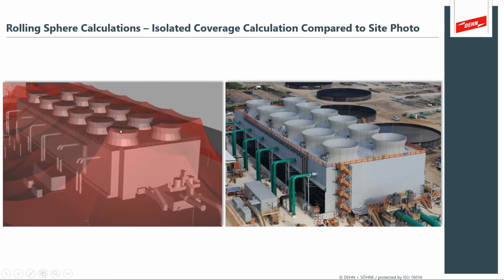So here's a nice illustration of the calculated coverage. This is what the theoretical coverage of that lightning protection system will provide, and then an actual photograph of the finished system. It's a little hard to see in this photograph, but you can see the air terminals are actually mounted on the light poles because the customer doesn't want us to apply a lot of extra poles and things across their structure. We want to be efficient, and we want to use the structure's natural light poles as part of our air terminals. And that leads you to the coverage model that you can achieve with such a design. And so what's nice is you get a really good correlation in your mind's eye of the air termination, the coverage model, and then how that will actually be achieved on the site.